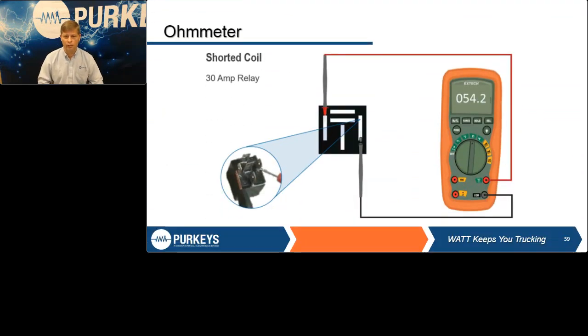We're going to grab another one here, though. Did the same check. This one comes back, it's only got 54.2 ohms resistance. So what that should tell you immediately, somewhere in all those loops of wire, you have two coils that are touching each other, so it's not going through all the loops anymore. So you have much less resistance.